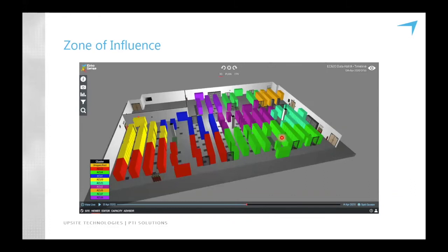Another really powerful aspect of the machine learning is the zone of influence. And so you can see in this image that each of the cooling units is colored and the cabinets that that cooling unit feeds have the matching color. So you can see in this row that there are three different cooling units feeding the cabinets in this row. These cabinets are fed by air that comes from this cooling unit. A couple of cabinets here are fed from air from this cooling unit. And this blue cooling unit provides cooling to these last two cabinets in the room.